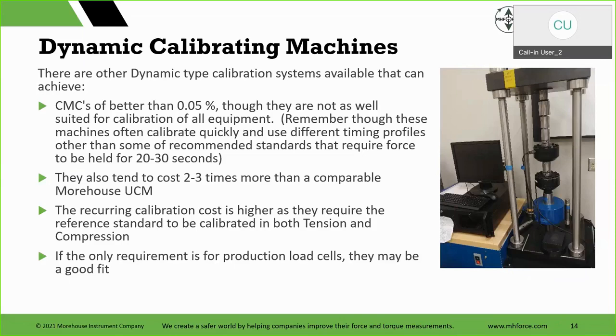And like I said, I'm not against them, they go fast. And if you're doing load cells for production, or if you can standardize that you're only going to receive X load cell and it's this range, because you still have a problem of changing standards. They go from about 10% of capacity up to capacity. So if this machine's 55,000, and you had a 50,000 pound force load cell, you could calibrate it from 5,000 to 50,000. If the customer expectation is to go lower, now you have to change out standards, which is, again, more cost, and because your CMCs are higher, more cost. The ISO 376 loading range isn't going to be as good, so it's not really well suited for that.